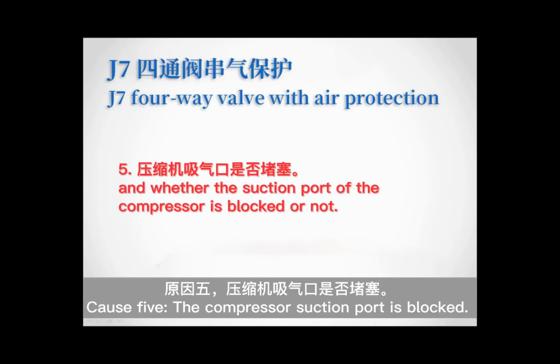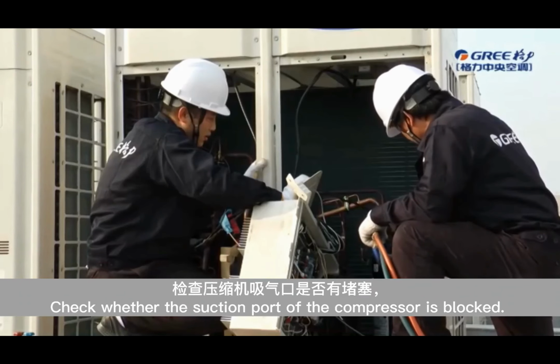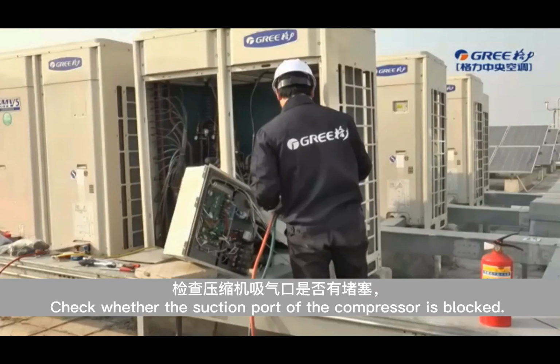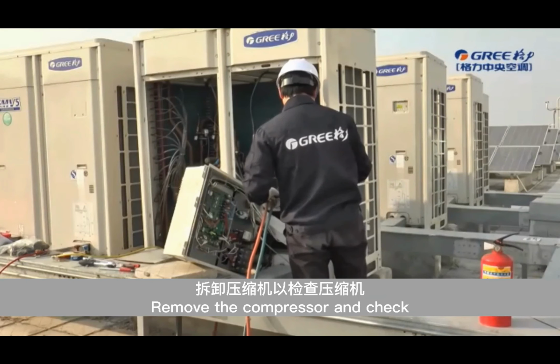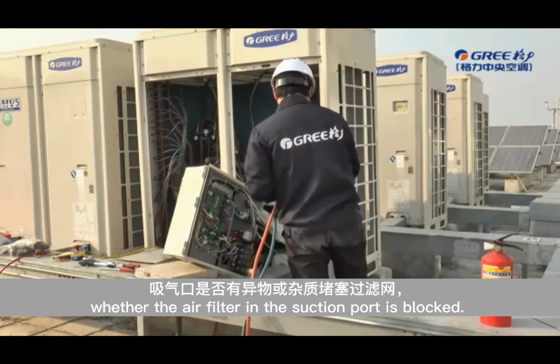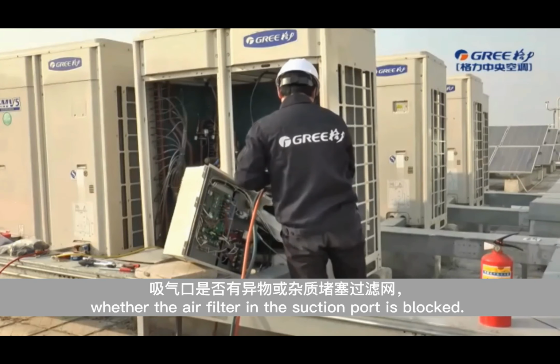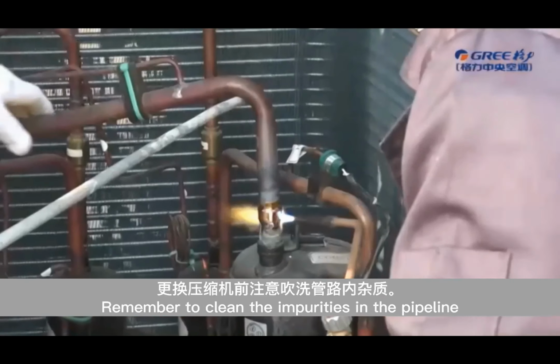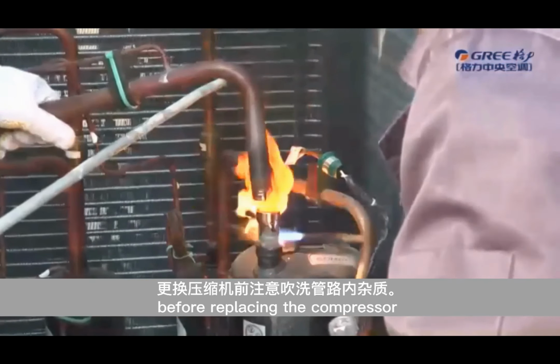Cause 5. The compressor suction port is blocked. Check whether the suction port of the compressor is blocked. Remove the compressor and check whether the air filter in the suction port is blocked. If blocked, replace the compressor. Remember to clean the impurities in the pipeline before replacing the compressor.